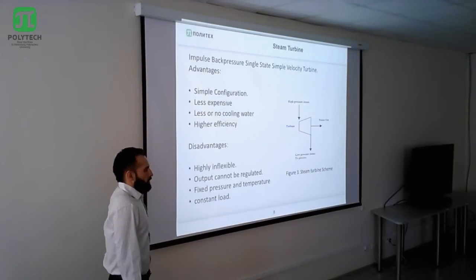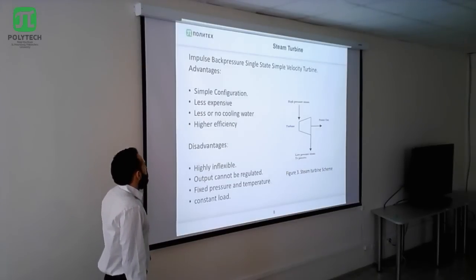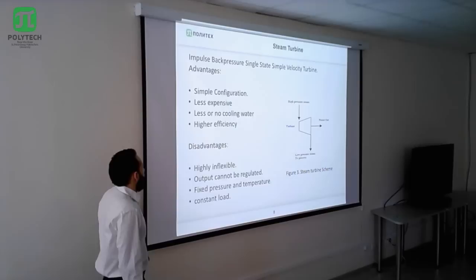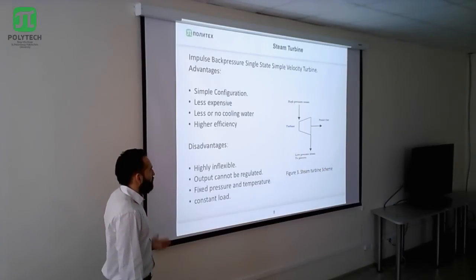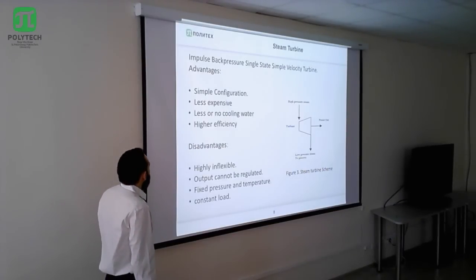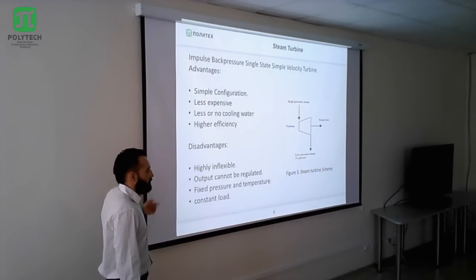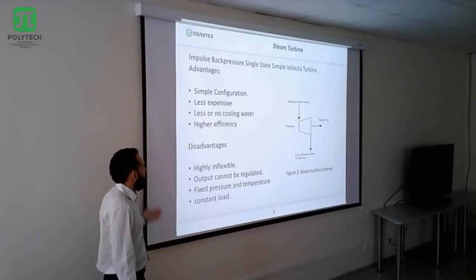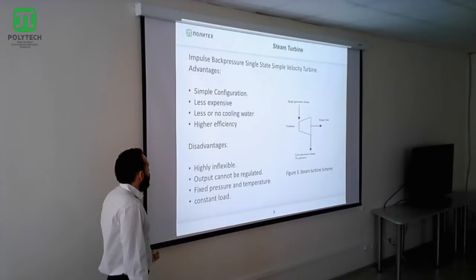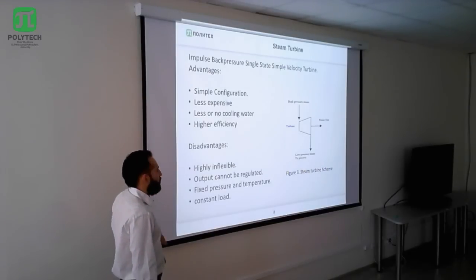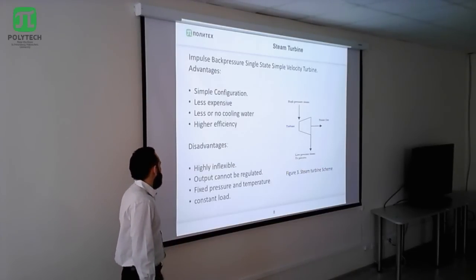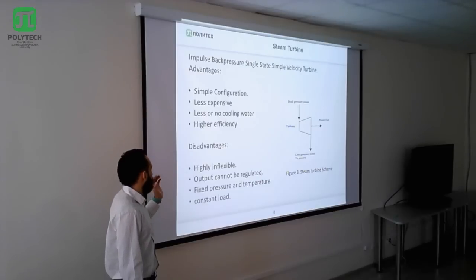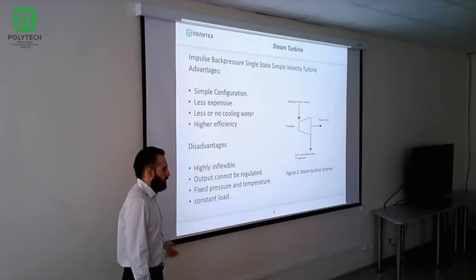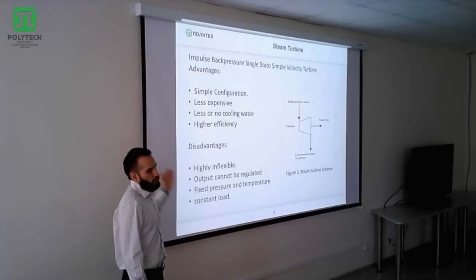The steam turbine I used for this purpose was an impulse back-pressure single-stage simple-velocity turbine. The advantages are that it's easy to configure, it's more efficient, and it doesn't need cooling water. The disadvantage is that it's inflexible; we cannot vary the output, and it cannot be regulated.